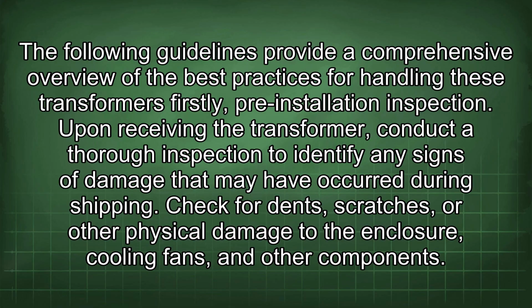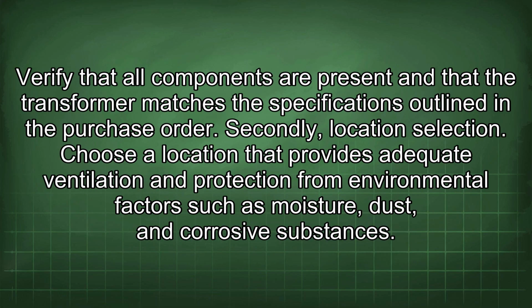Firstly, pre-installation inspection. Upon receiving the transformer, conduct a thorough inspection to identify any signs of damage that may have occurred during shipping. Check for dents, scratches, or other physical damage to the enclosure, cooling fans, and other components. Verify that all components are present and that the transformer matches the specifications outlined in the purchase order.